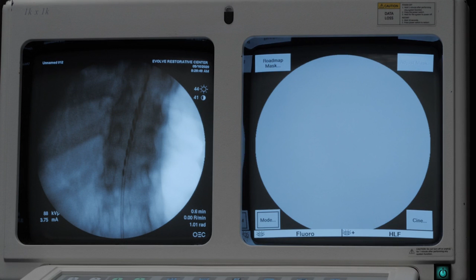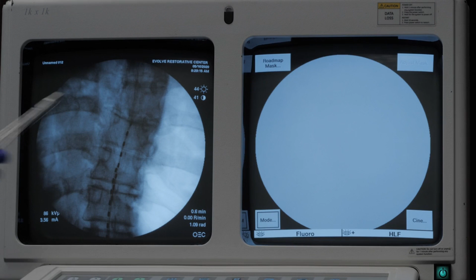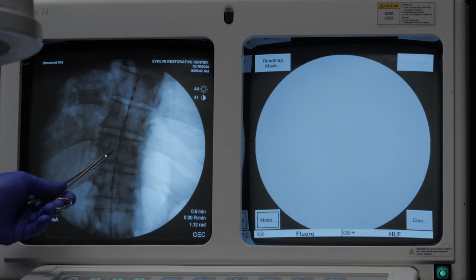So we stagger the contacts just to make sure that we can cover as much surface area for some microprogramming if it's necessary. And that lead placement looks pretty good to me. And at this point, you can see the first lead is at the top of T8. The second lead is in the mid body of T9. And we just need to get a lateral to make sure that the leads are in fact placed in the dorsal epidural space. Now, even with 20 years of experience, the leads could potentially go ventral from time to time.